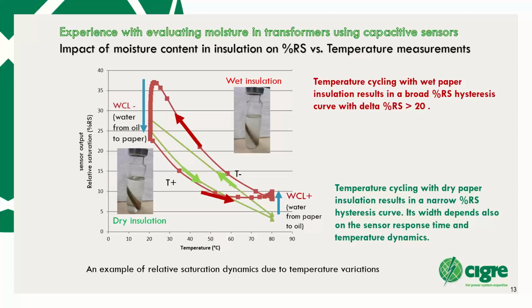The problem is that actually the oil is nonpolar and paper is polar. That means that the moisture which is dissolved in the oil cannot go very quickly back into the paper. It tries to do that, but it cannot do it so quickly. Therefore, it's something like raining in the oil. This straight line, what you see here. After a certain time, enough time, of course, moisture will go back into the solid insulation, and you'll have again an oil which is clear, but it takes a lot of time. So in this graph, we can see that solid insulation which is wet has a very broad hysteresis curve.